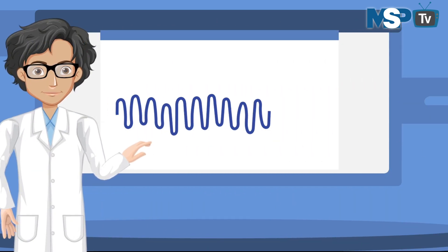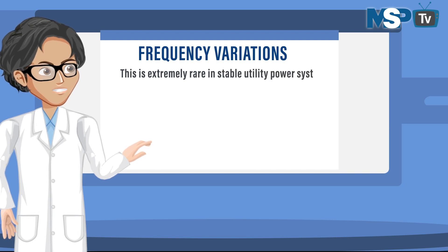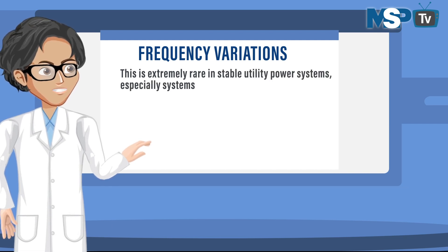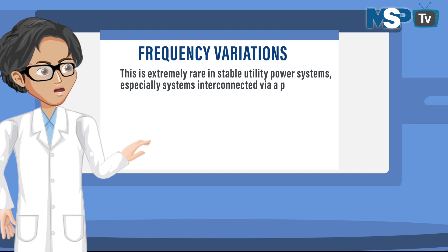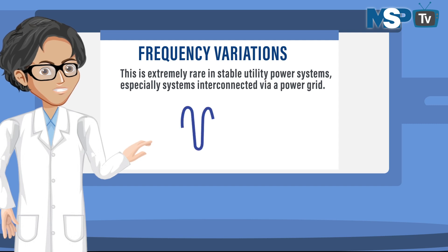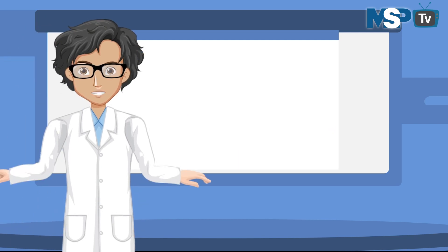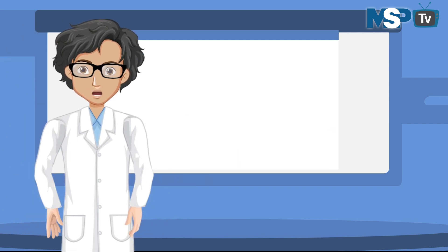The last type of power problem is frequency variation. This is extremely rare in stable utility power systems, especially systems interconnected via a power grid. However, for sites that have dedicated standby generators or poor infrastructure, frequency variation is more common — especially if the generator is heavily loaded. IT equipment is generally frequency-tolerant and not affected by minor shifts in the local generator frequency. So these are the most common power problems — I hope I have provided some valuable information.